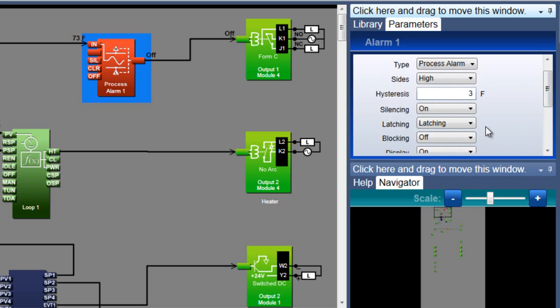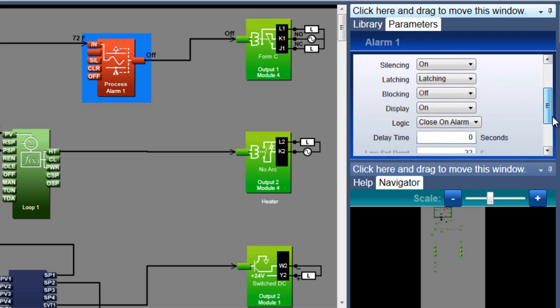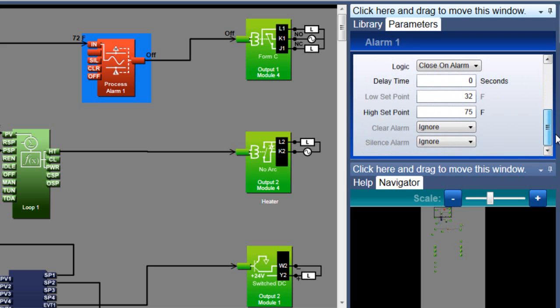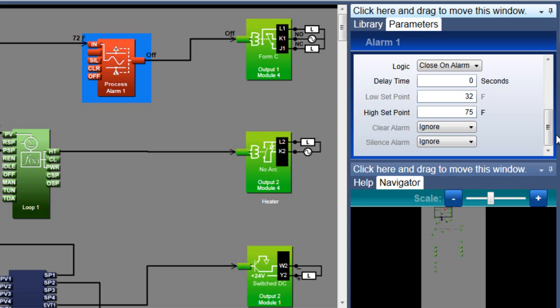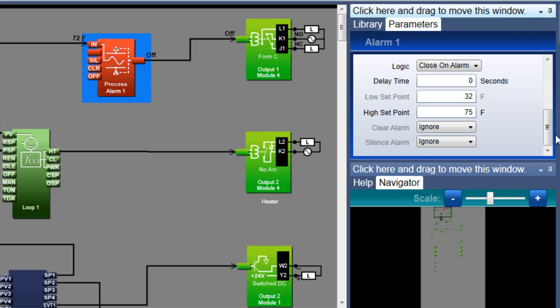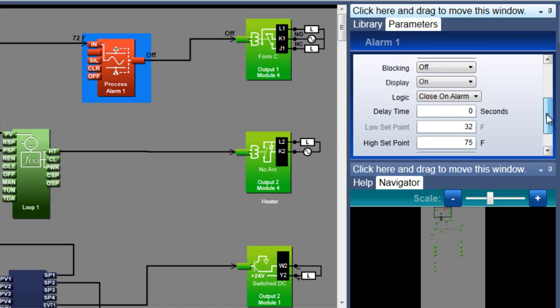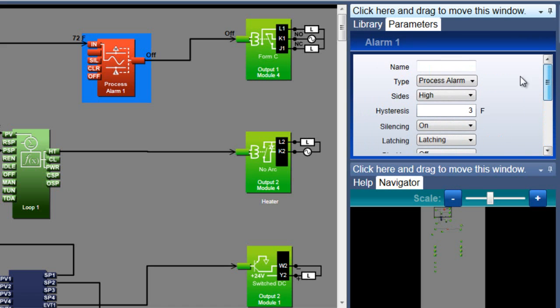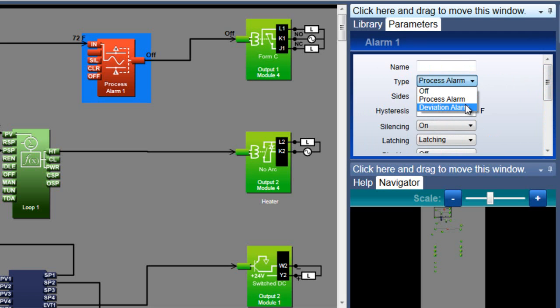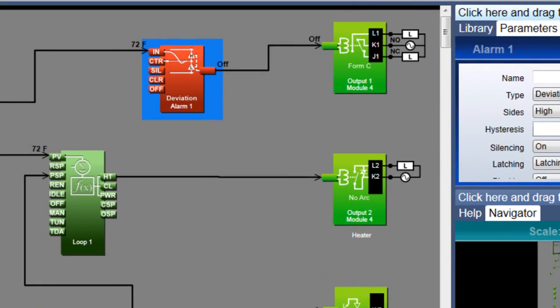So far, we've been looking at how a process alarm works. For a process alarm, you set the high setpoint and low setpoint directly, or absolutely. I set the high setpoint to 75 degrees, and the alarm occurs at 75 degrees. To make the alarm relative to another value, I'll change the type to deviation alarm.